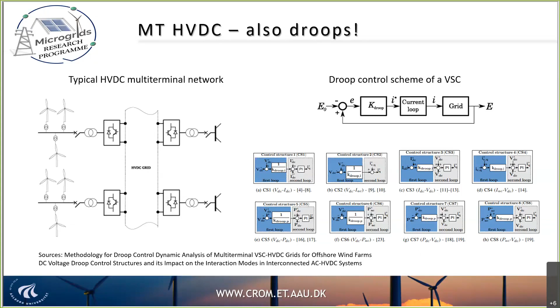There are many ways to implement droop control for these VSCs that conform the HVDC system, like using voltage and current loops, or voltage loops without integrators. So you just droop it down using sometimes current or sometimes power instead. But finally, all these concepts come down to voltage versus current or power droop. This is basically the control that we can see nowadays that is massively applied. I won't say we have something already done, but it's right now in the research phase.